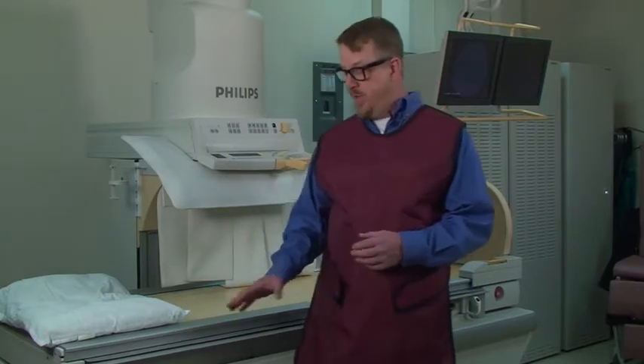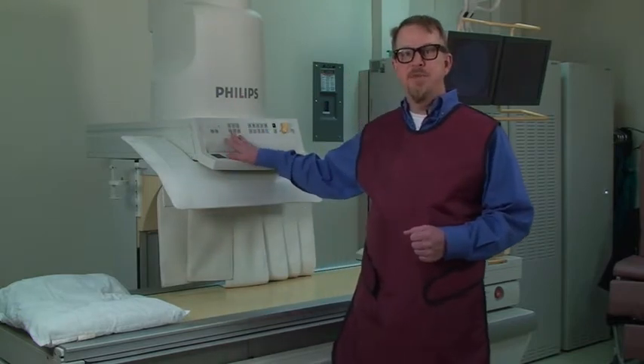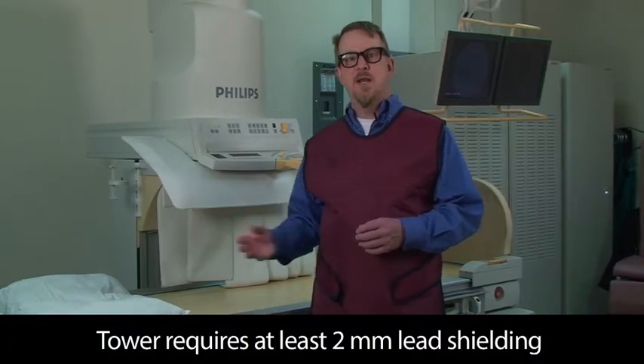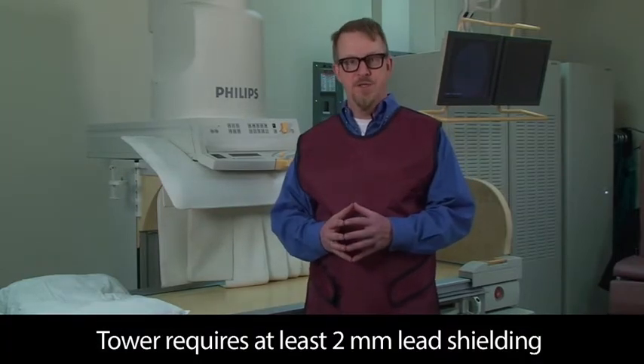Fluoroscopy equipment has built-in protection. Traditionally, the X-ray tube is located within the table. Although some models may have the X-ray tube over the table, both types have the requisite housing to prevent radiation leakage. If the tube is located within the table, the tower is situated above the patient, or in front of the patient if the table is positioned vertically, and contains the image intensifier or the receptor. Considered a primary barrier, the tower requires at least 2 millimeters of lead equivalent shielding.